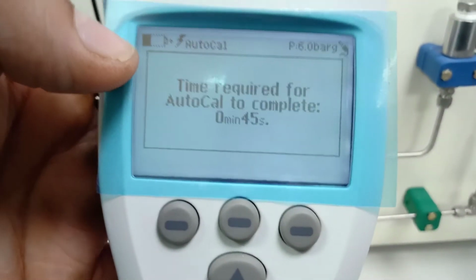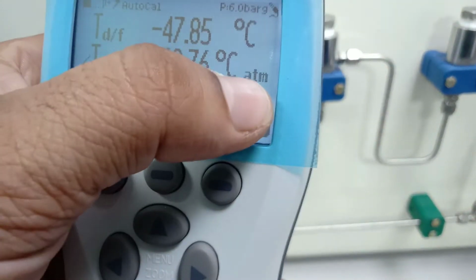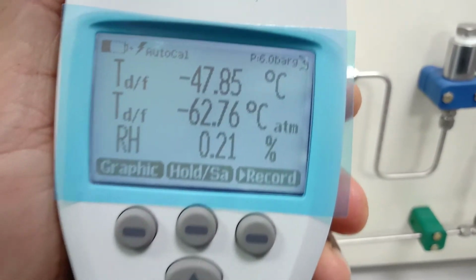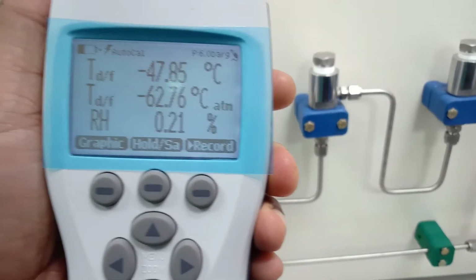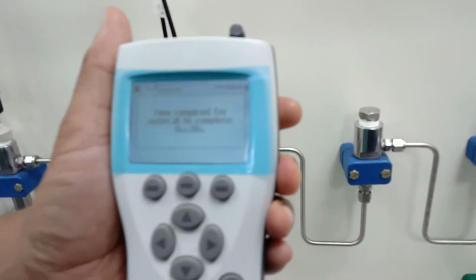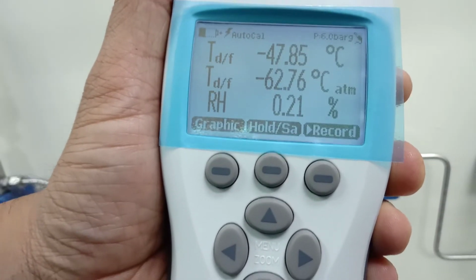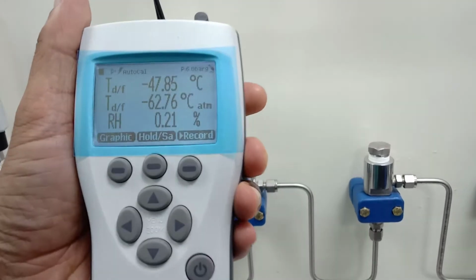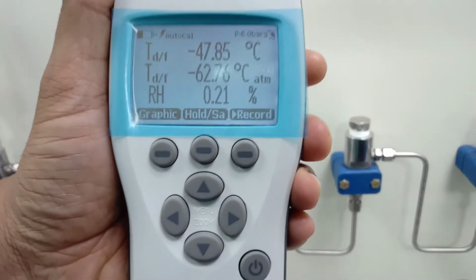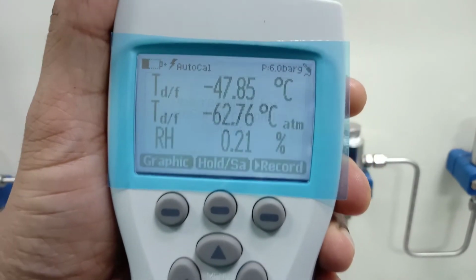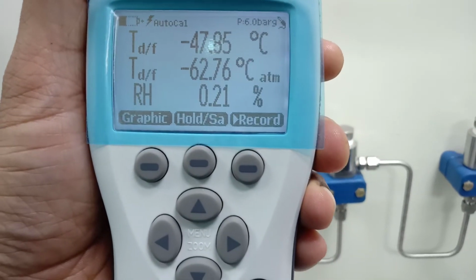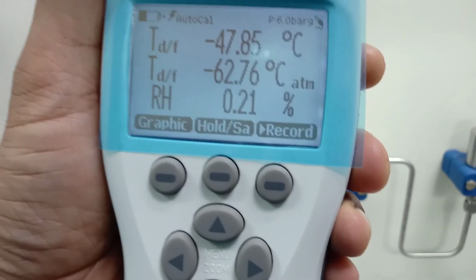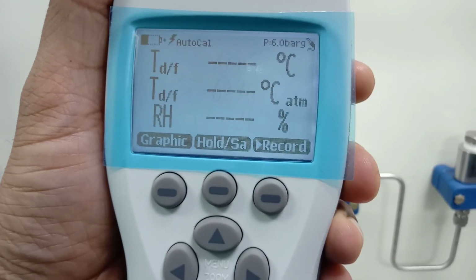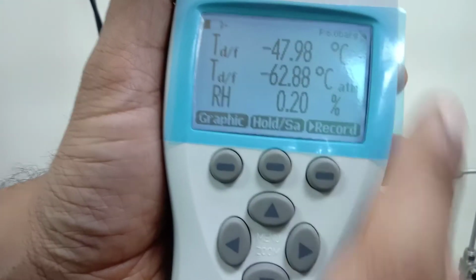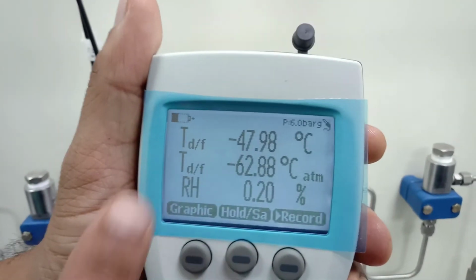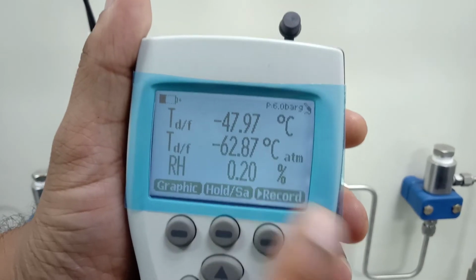So this is the dew point, and then we have this atmospheric dew point. So this is also very important in GIS dew point measurement. So in a pressurized process, when you leak the gas in the atmosphere wherein no moisture is added, the dew point will be minus 62.76. If that gas is in the pressurized process, say at 8 bar, and it is put into different conditions at 1 bar without any moisture addition, then the dew point will be minus 62.76. So auto calibration is about to get completed. You can see the pressure is also there. So now this is the dew point, and this is atmospheric dew point, and this is the relative humidity.